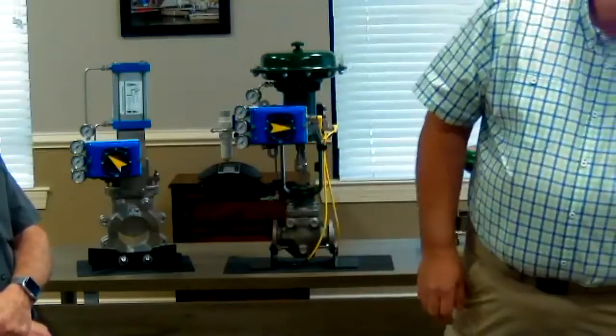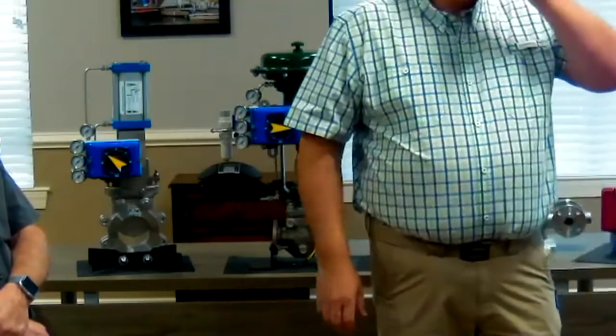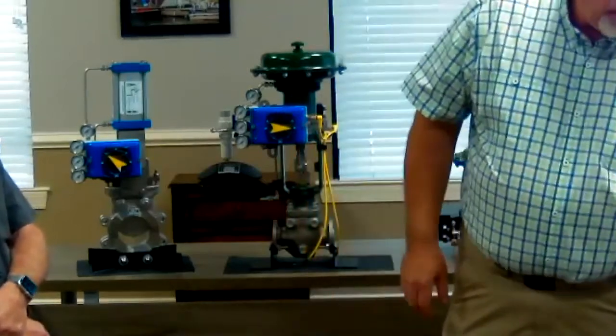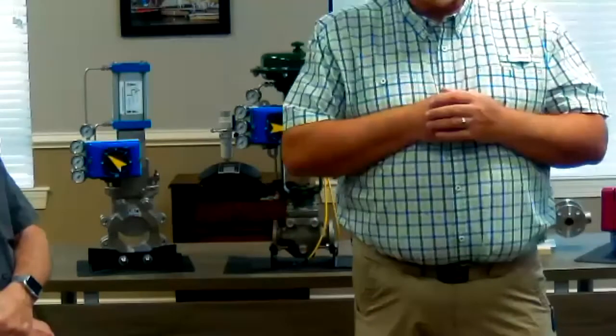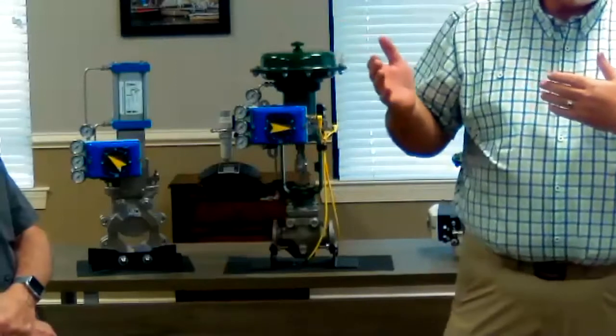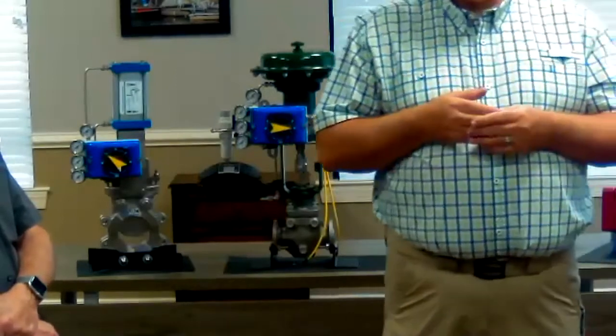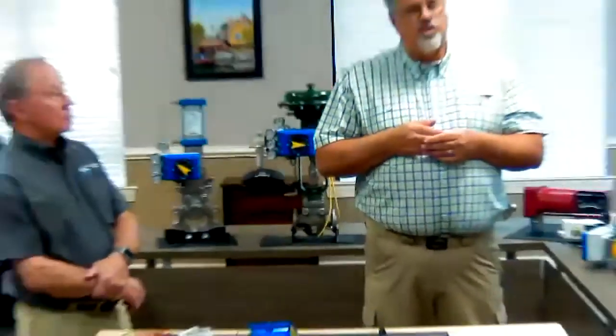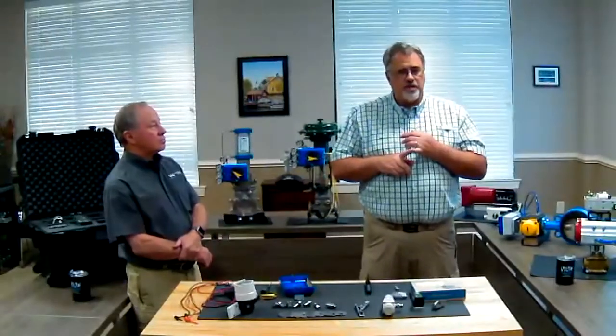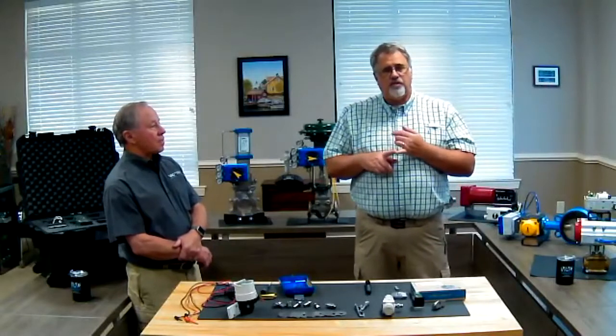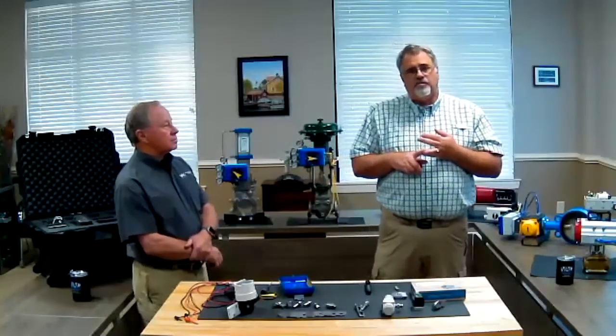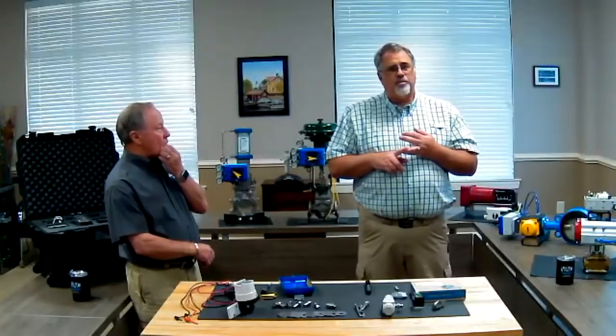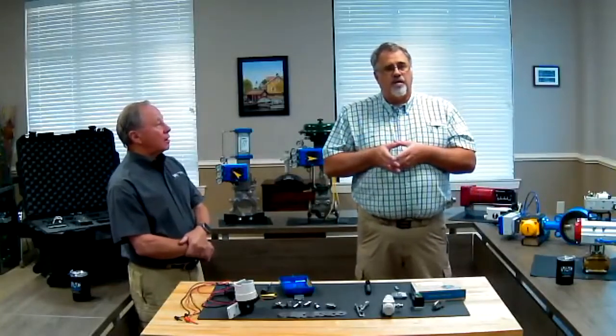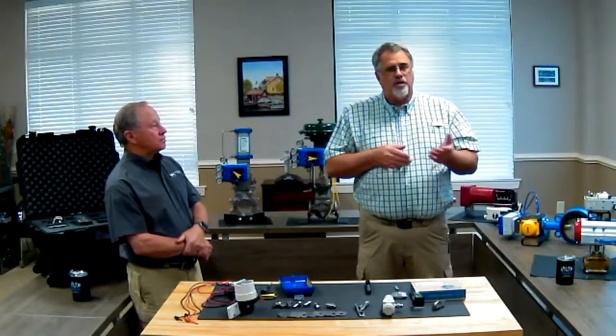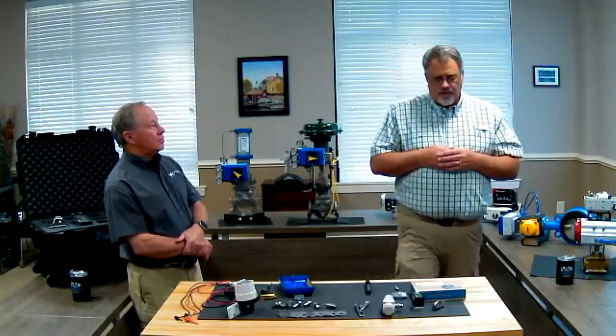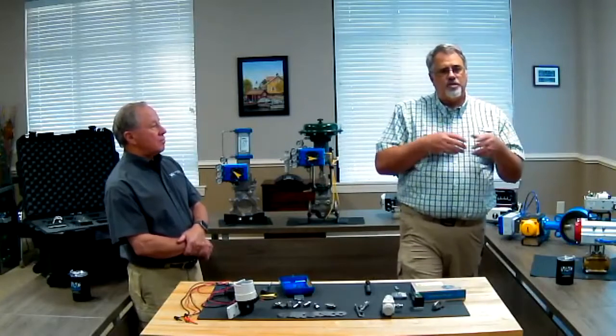The question was, can we do this while the valve is in the process? So when you say do this, I'm assuming you mean install a positioner on an existing valve. Yes, you can. The only concern is there's some safety issues that you need to be aware of with the plant, and the plant is going to tell you about that. It is a requirement to properly calibrate the positioner to be able to stroke the valve.